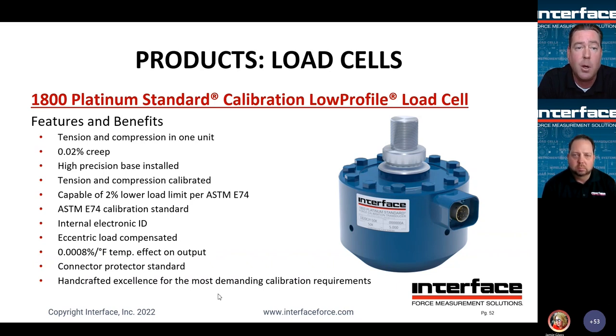And these also would come standard with an ASTM E74 calibration, and provided that the calibration is sufficient, it is capable of a 2% lower limit factor per ASTM E74. And again, this is our highest grade of metrology calibration grade force transducer. Yeah, next slide, please.